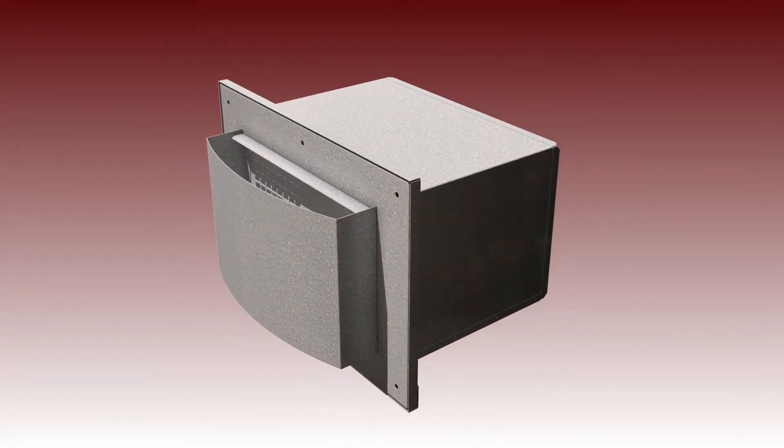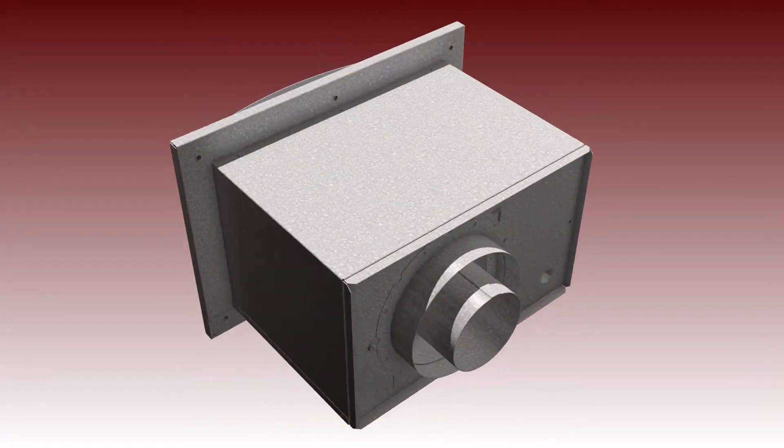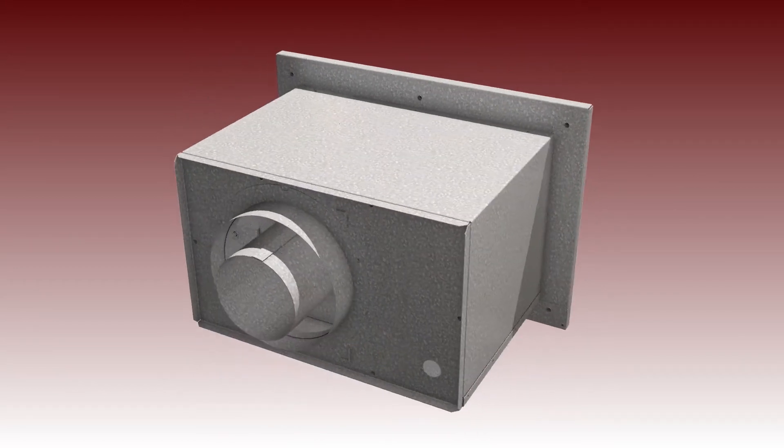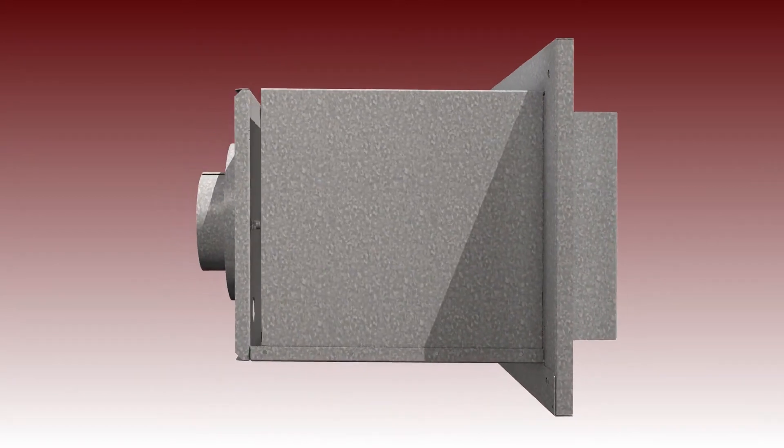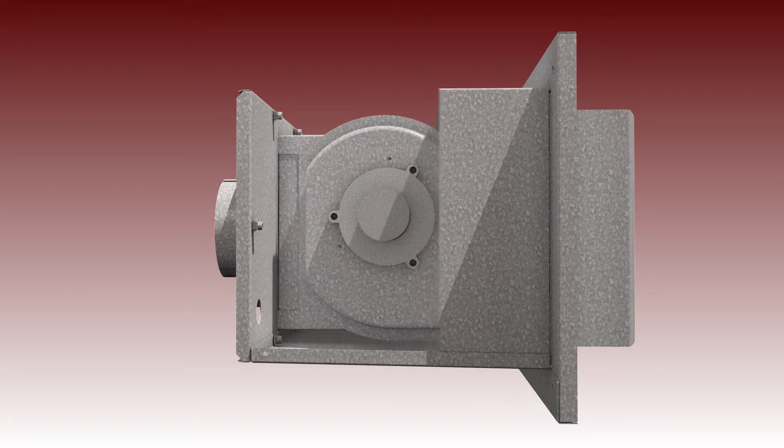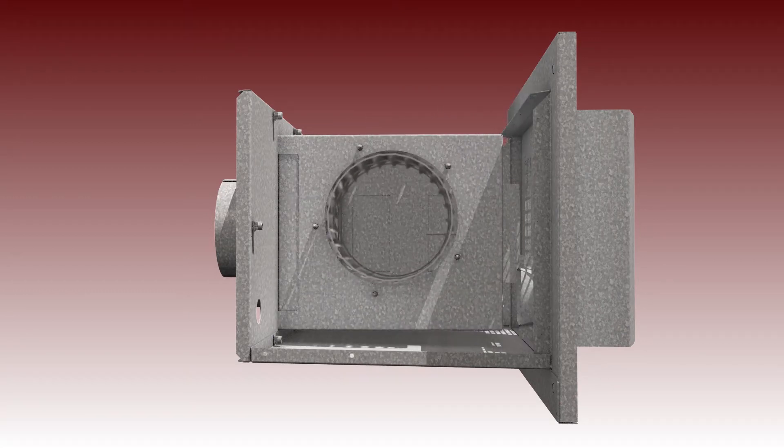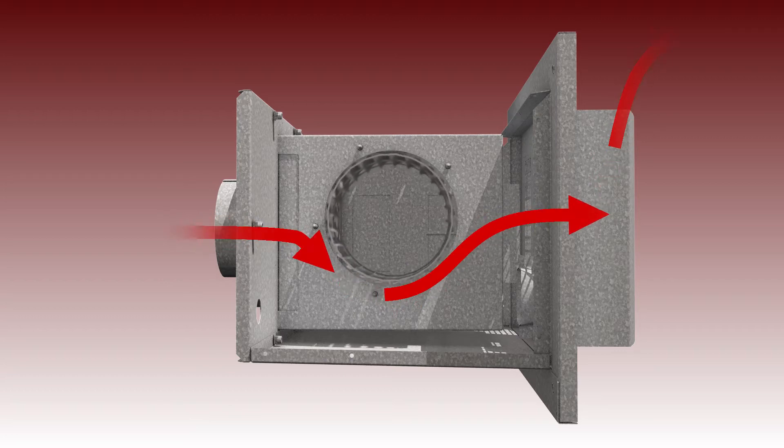A power vent accessory may be necessary for applications requiring long vent runs or multiple elbows. Inside the power vent, a quiet, powerful blower expels combustion gases, which creates negative pressure in the fireplace that draws in cool outside air to support combustion.